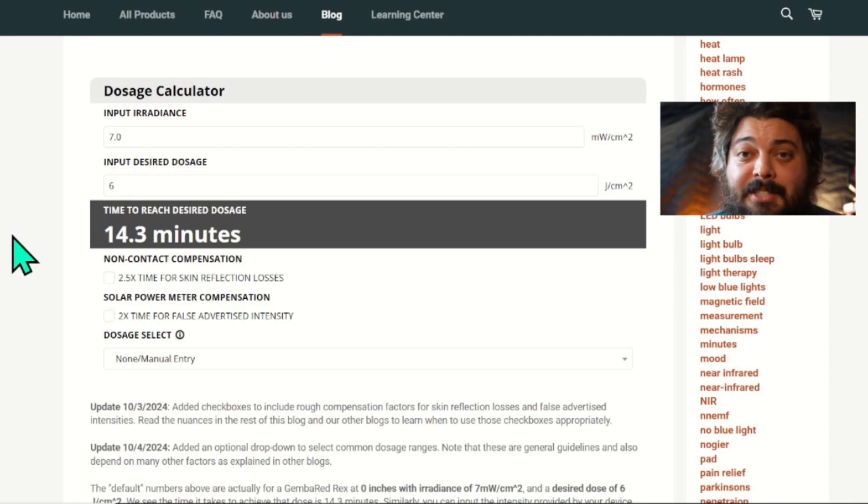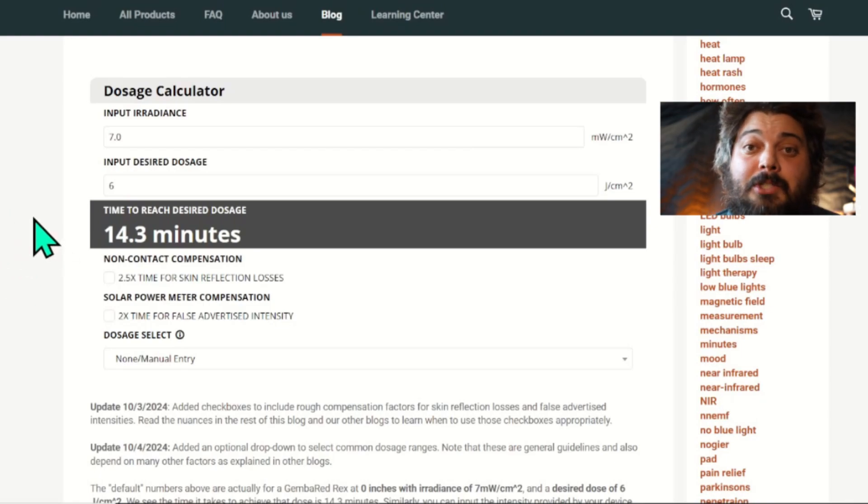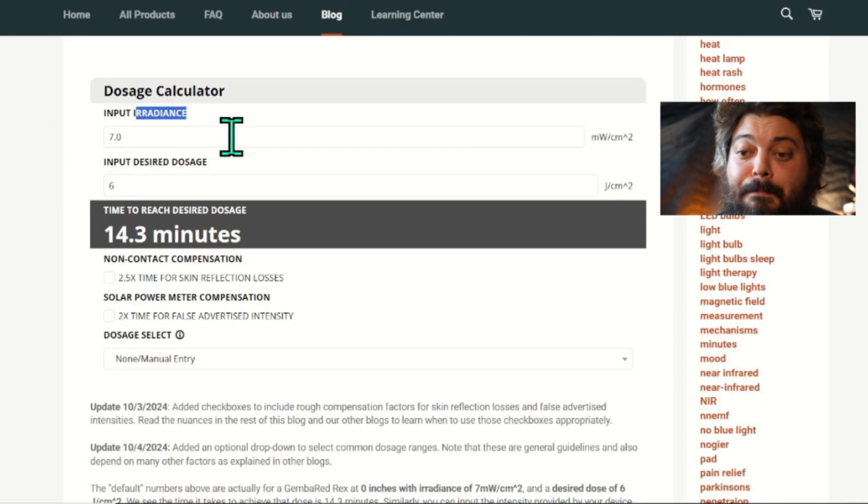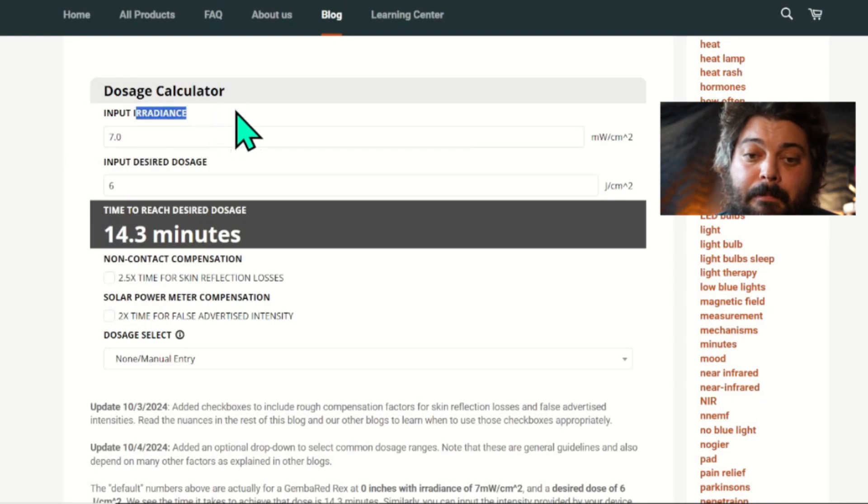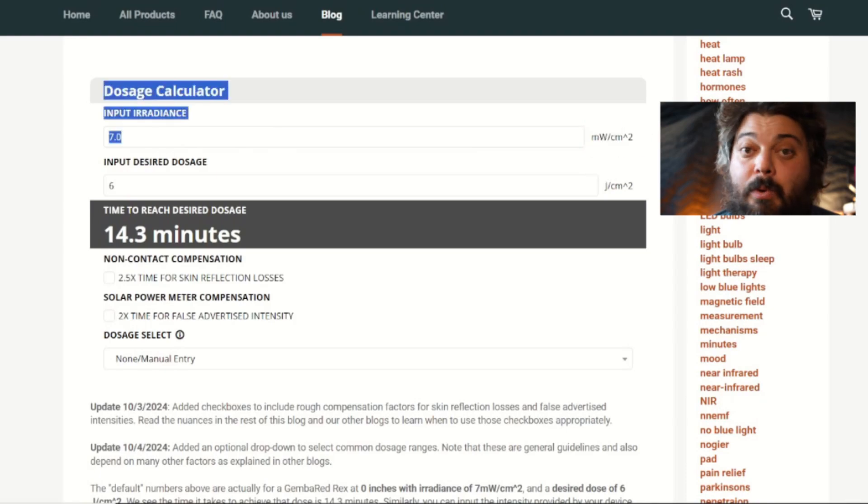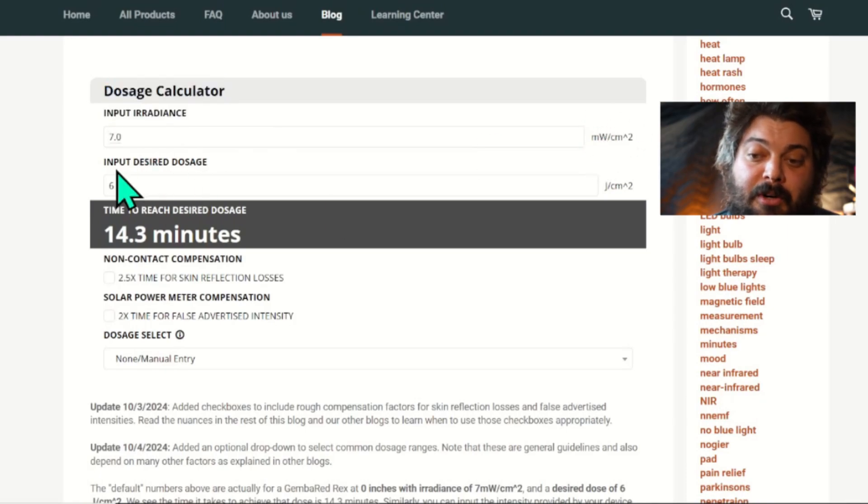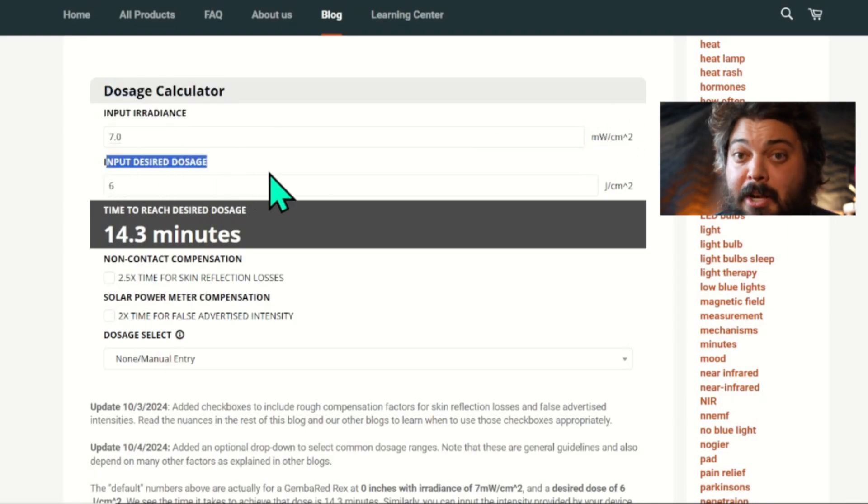But in concept, it's very simple. You input the irradiance—sometimes it's called the intensity or the power density—and the units are in milliwatts per centimeter squared. Then you input what dosage you want, and those units are in joules per centimeter squared.